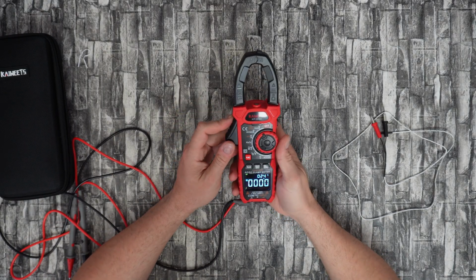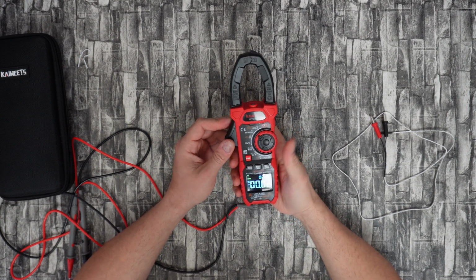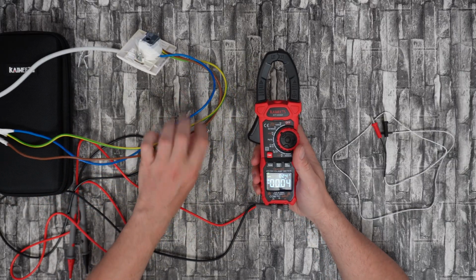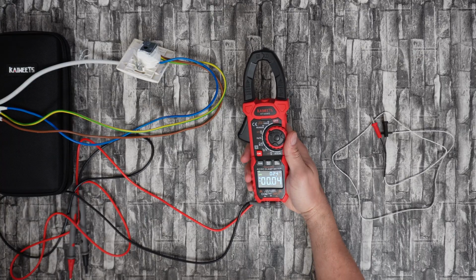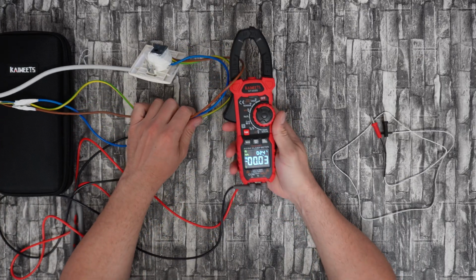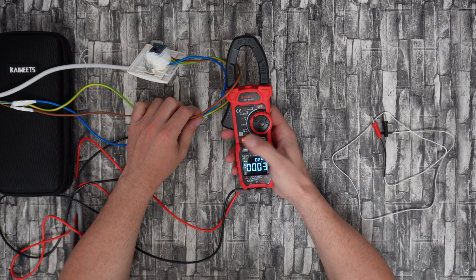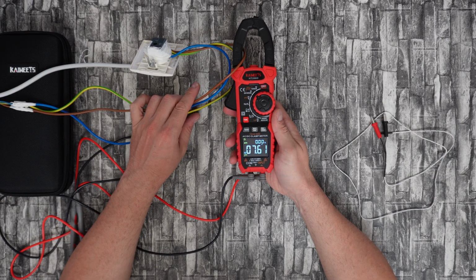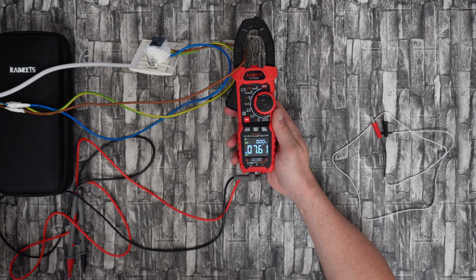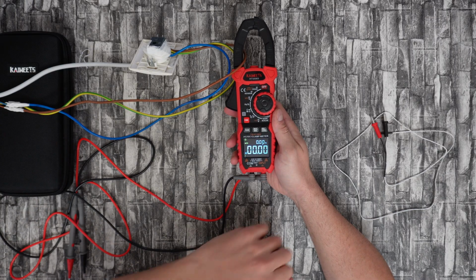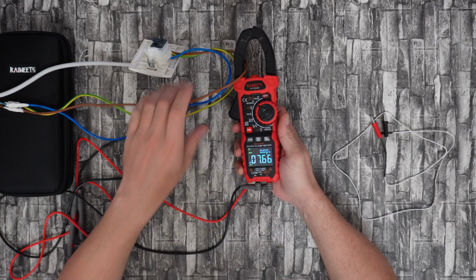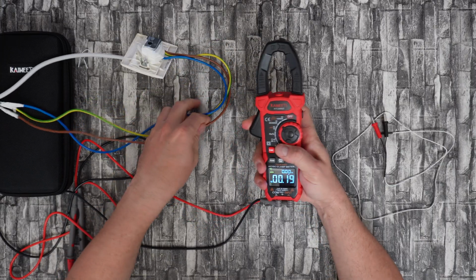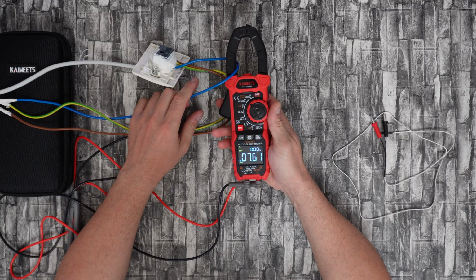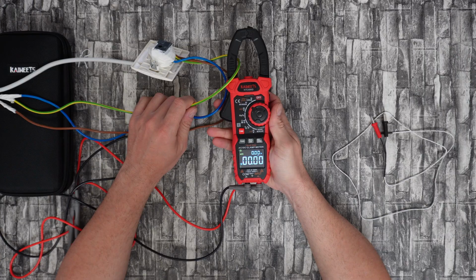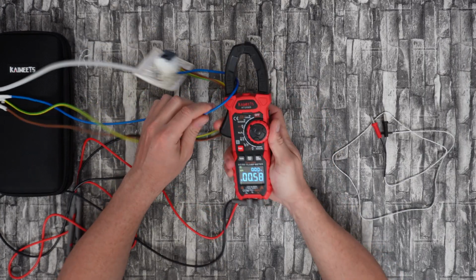Now let me show you how you can measure the amp with a clamp. I have installed my boiler. 7.6. If I will switch it off... on again, there it is. So you can't have all the cables inside the clamp, you need only one cable every time, but not the ground cable, neutral or the phase, the live cable.